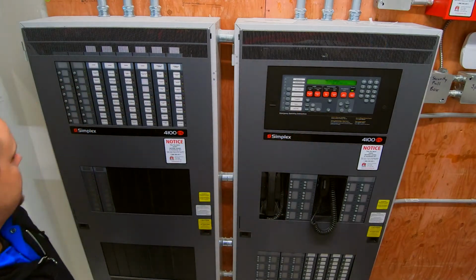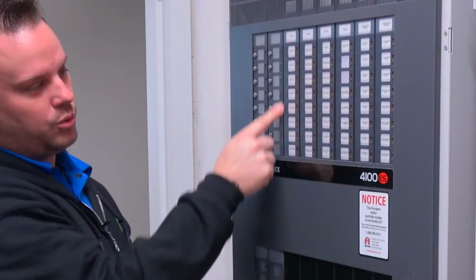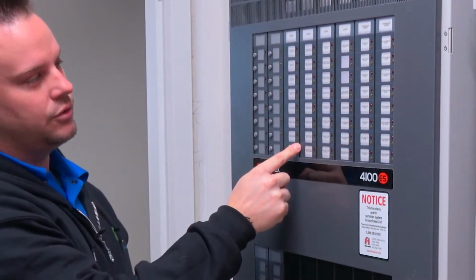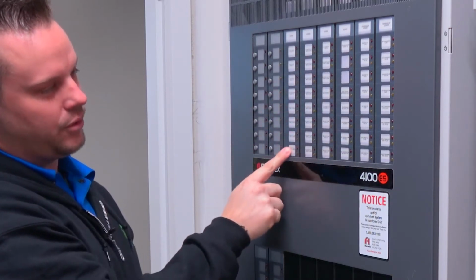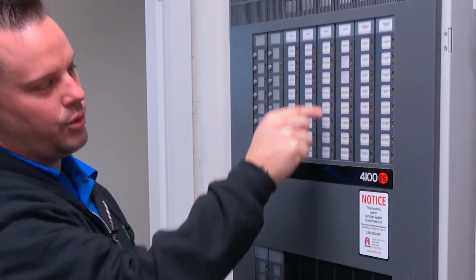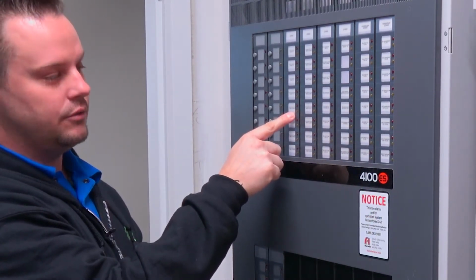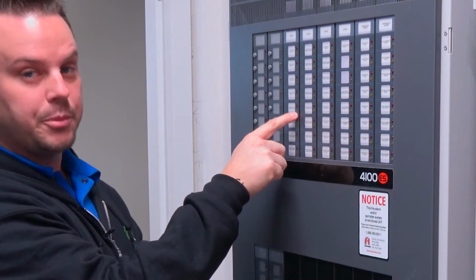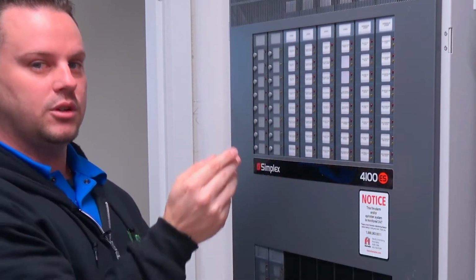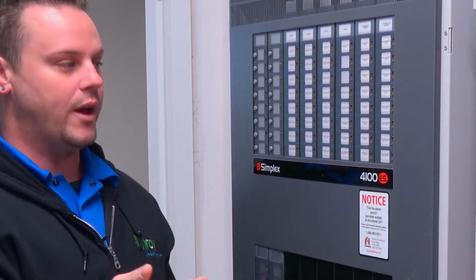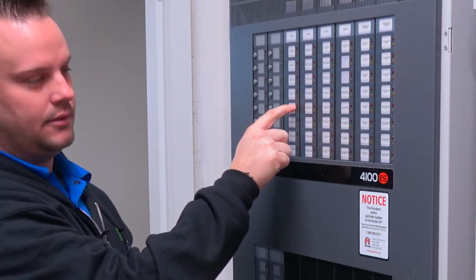And then I'll be going over this side here. These are basically all your zones in your building. So it basically starts from top of stair, and then it goes down to the 4th floor, and then to 3, 2, and 1. When you have a smoke alarm in a residence unit, you're going to get a supervisory in the panel, so that's going to light up your amber light. If you had a smoke detector in the hallway or a pull station pulled in the hallway, you're going to be lighting up your red LED.